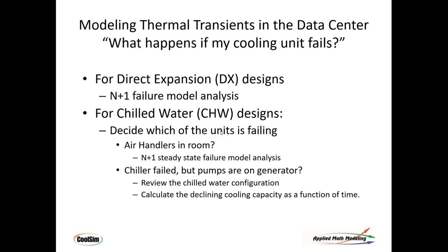There are basically two kinds of data center cooling systems. One is a DX (direct expansion) unit — a one-to-one relationship between the unit in the room, which has a compressor, and a condenser in the outside atmosphere. The evaporator is directly exposed to the room heat. If you have all DX, CoolSim can handle it today with N+1 failure mode analysis, automated so you can set up N number of runs with specific units switched off, returning a full set of results.